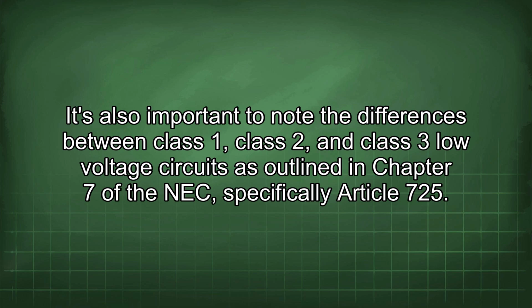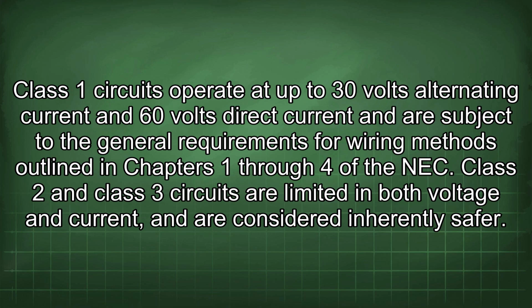It's also important to note the differences between Class 1, Class 2, and Class 3 low-voltage circuits as outlined in Chapter 7 of the NEC, specifically Article 725. Class 1 circuits operate up to 30 volts alternating current and 60 volts direct current and are subject to the general requirements for wiring methods outlined in Chapters 1 through 4 of the NEC.